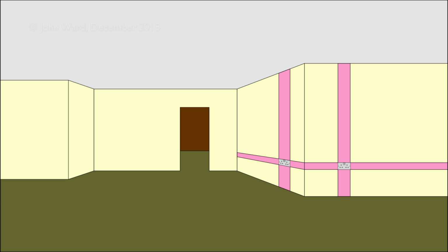Now of course if you wanted to extend the zone around the corner, then the easiest method is just to put another socket on the next wall, so that's what we've got here, and you have to see that creates its own zones as well, and then of course you can continue the cables around that corner and connect them to the next socket. So perfectly fine to put cables horizontally all around a room if you had sockets on all of the walls.